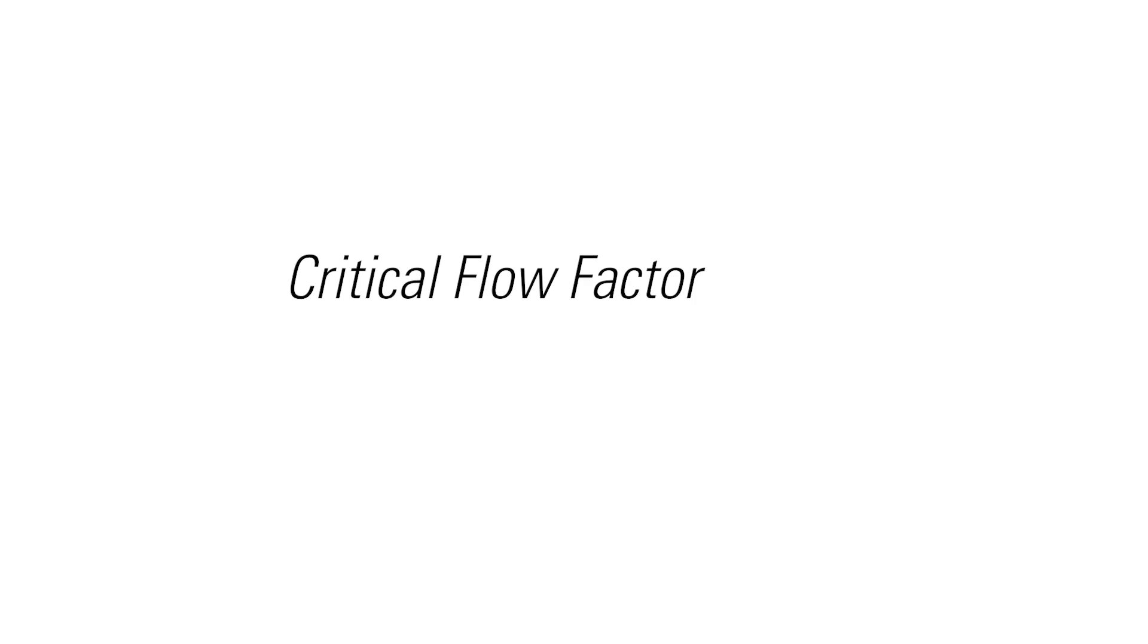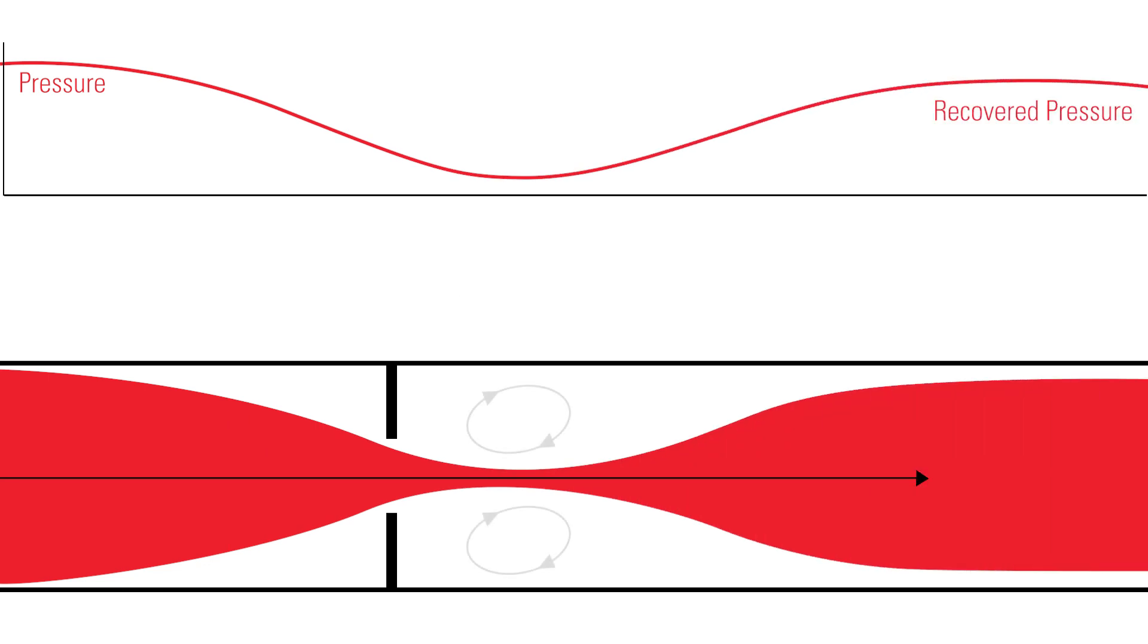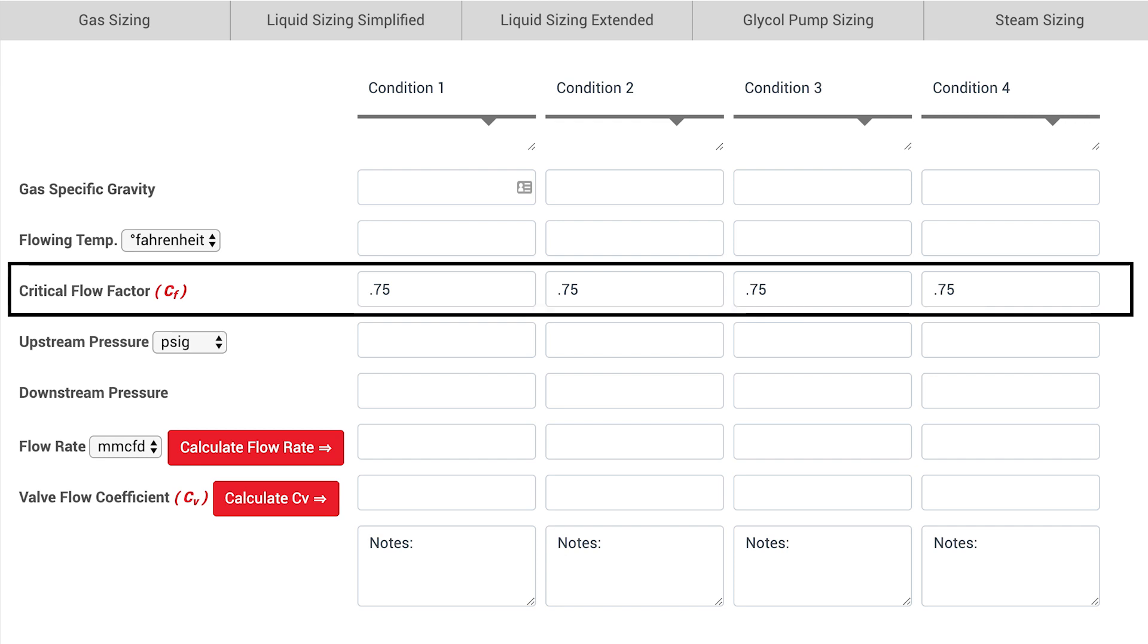Critical flow factor, often referred to as CF, is a coefficient that defines how pressure will recover after it drops to its lowest point inside the control valve. CF is needed in order to calculate flow coefficient and volume flow rate for valve sizing purposes.